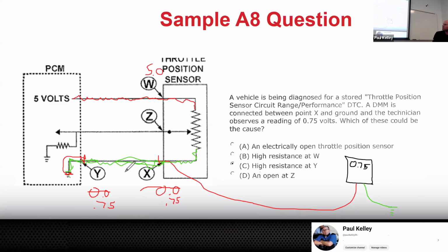Nothing, doesn't really talk about X. Let's see what we got for Y. What's that say? High resistance. Hey, doesn't that answer that for you? We got high resistance at Y. What is Y? Well, I don't exactly know. Let's say Y is a male terminal going into a female terminal, and there's corrosion here from water intrusion. That would be resistance. That would leave 0.75 volts right there, because it would be dropping the 0.75 on this connection. Make sense? So this wouldn't drop the full 5. It would save 0.75 because it's like, hey, we got to pay another toll up ahead because there's unwanted resistance. Make sense? Okay, cool. But let me explain this just a bit more.